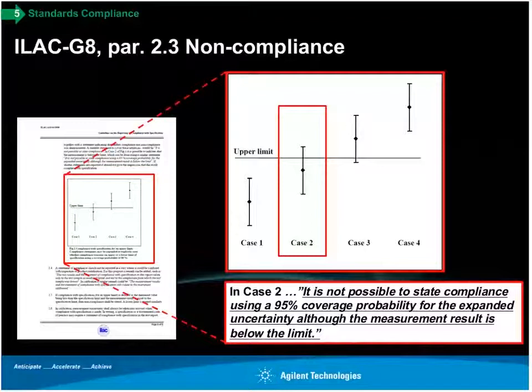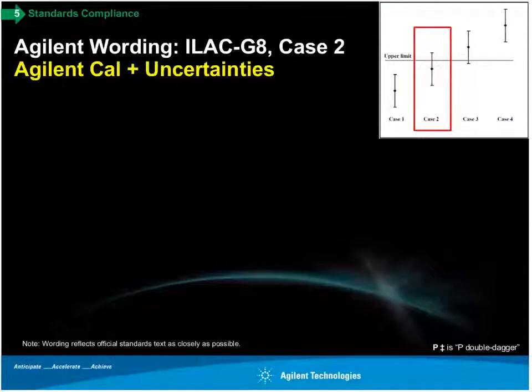Paragraph 2.3 is particularly important, so let's zoom in on that for a second. In ILAC G8 they have 4 different cases, which you can see here visually, and case number 2 is the one that causes the most angst and discussion. In that case, the measured result is inside a specification, however a portion of your measurement uncertainty is outside. What they tell you is that it's not possible to state compliance with an associated 95% coverage probability. That's what you're supposed to do. So this is the official guidance from that document.